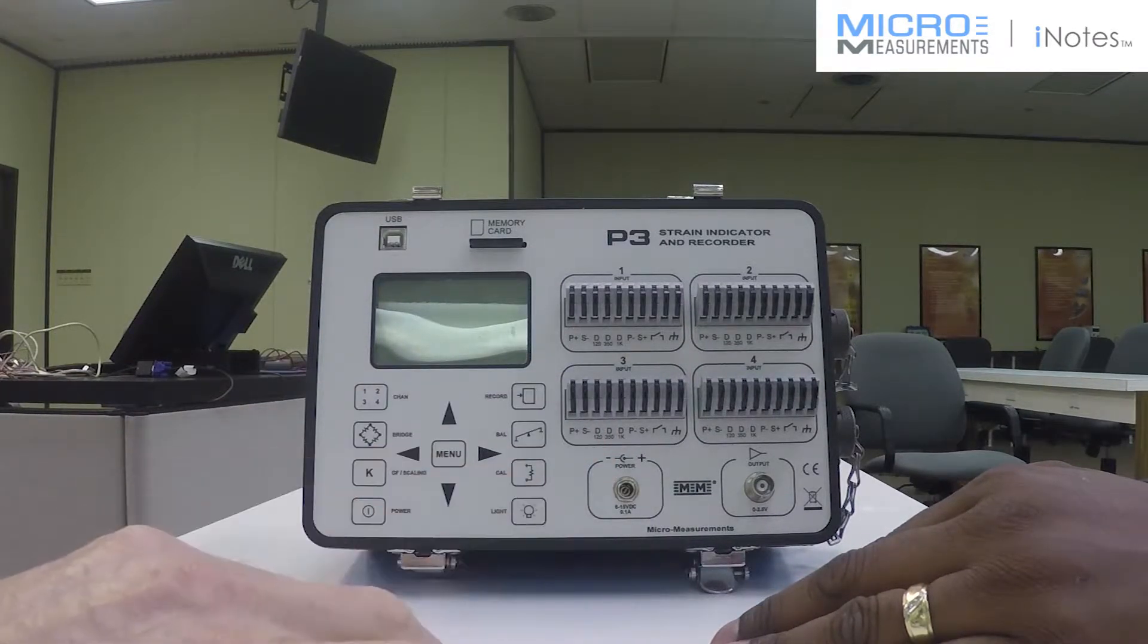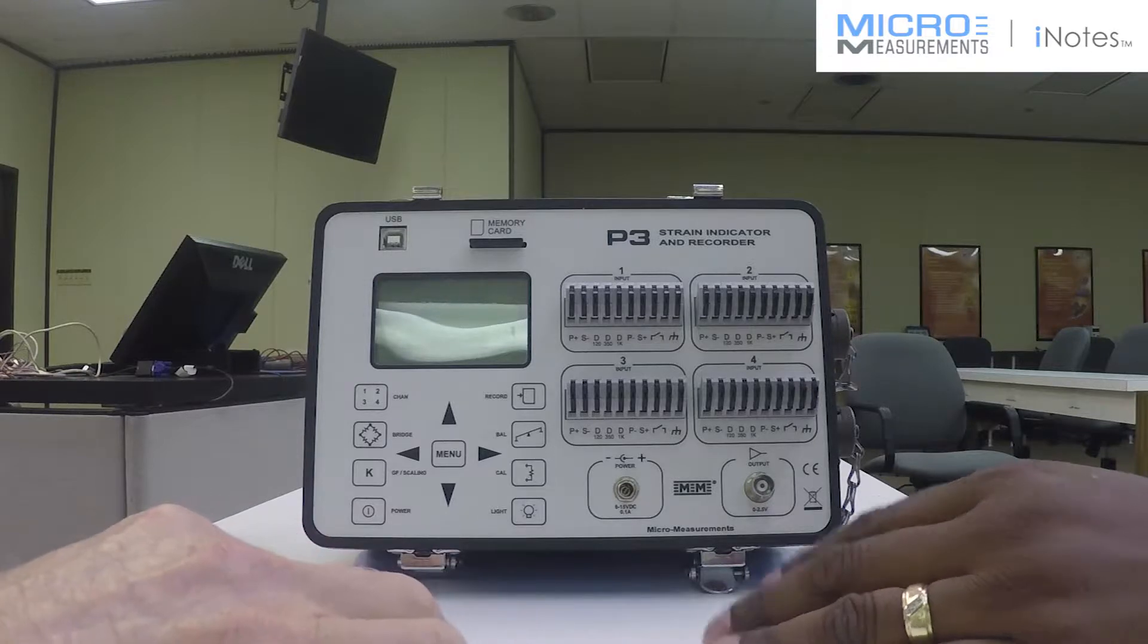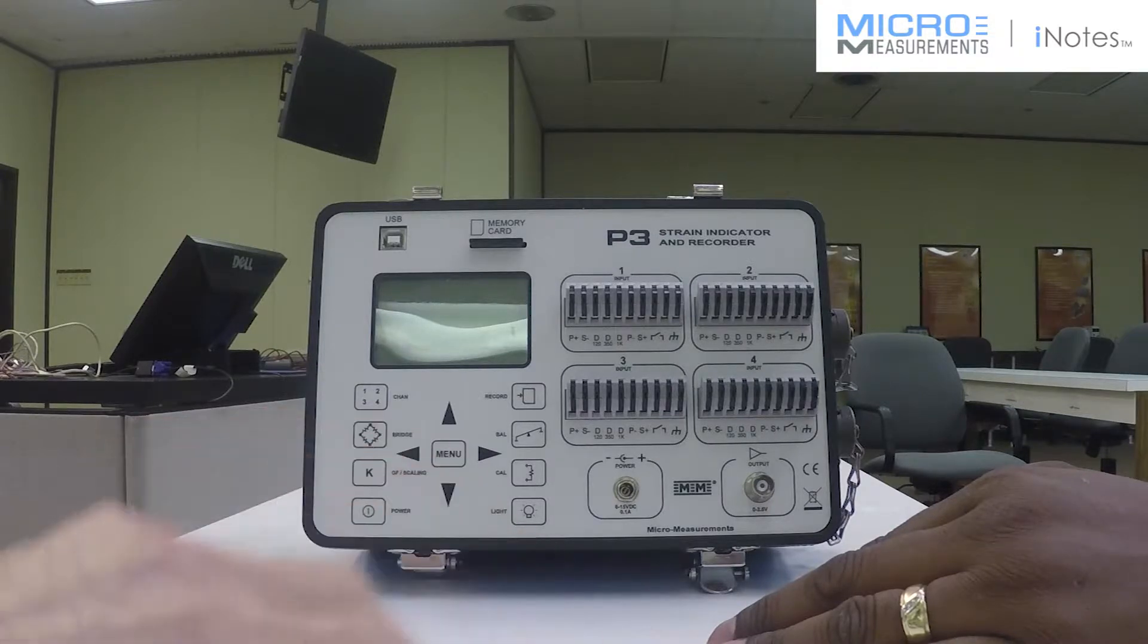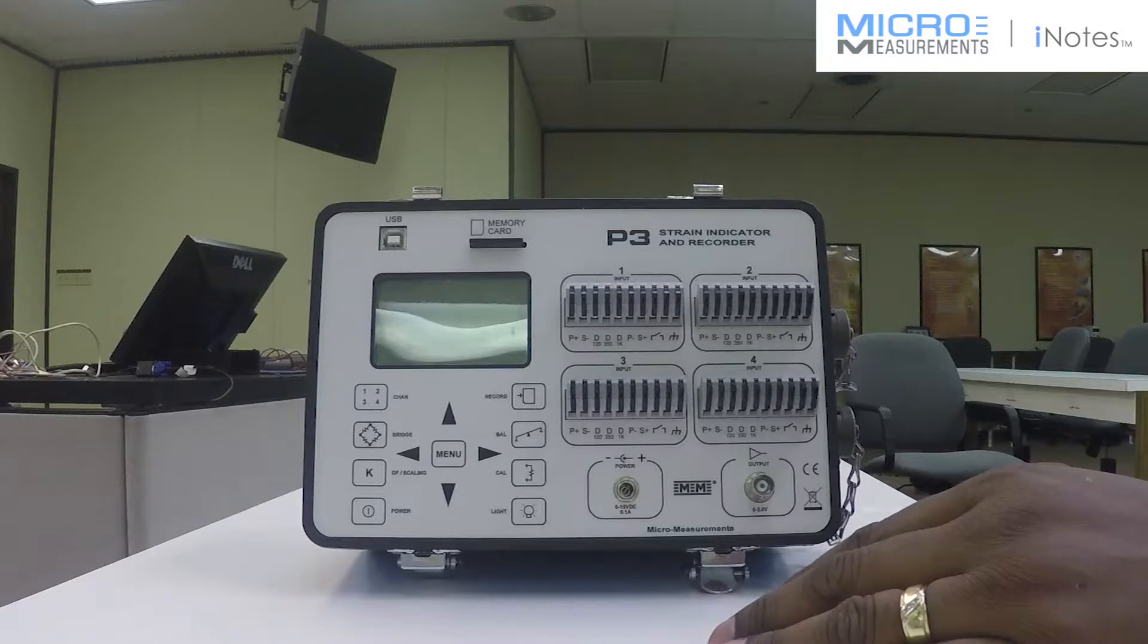Okay Danielle, tell me about this model P3 test instrument. Well Greg, the P3 is a lightweight portable strain indicator. How many channels of data can you take with this instrument? You can take anywhere from one up to four channels of strain gauge related data.